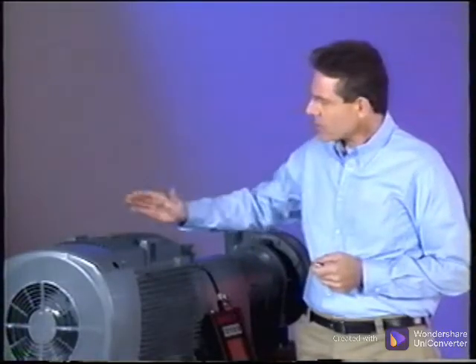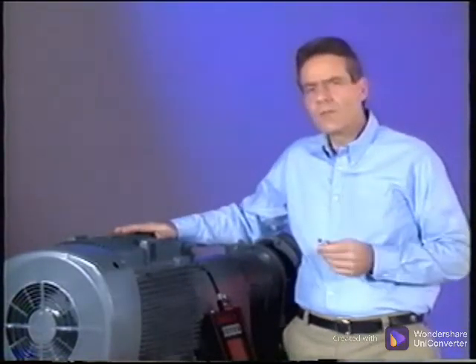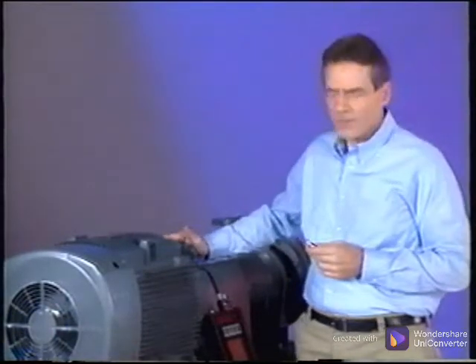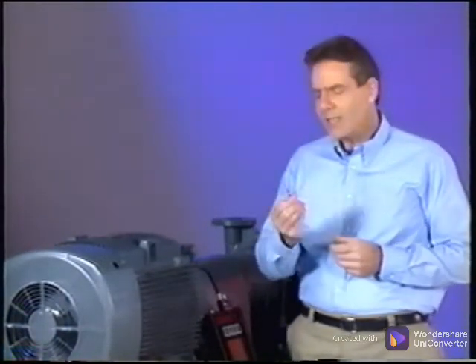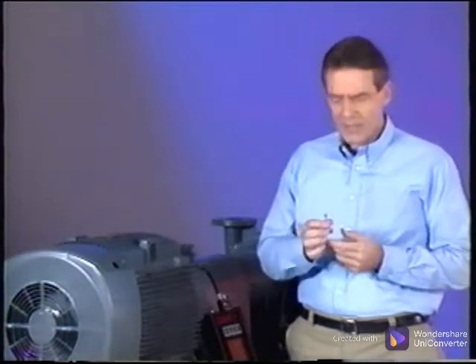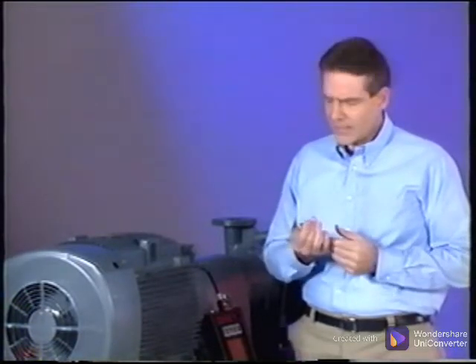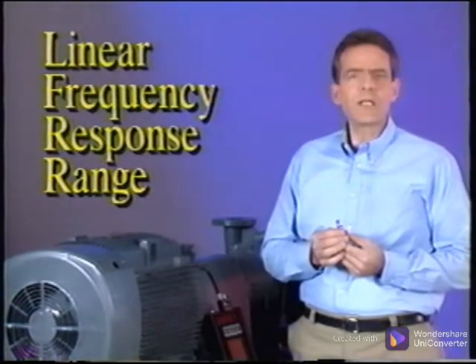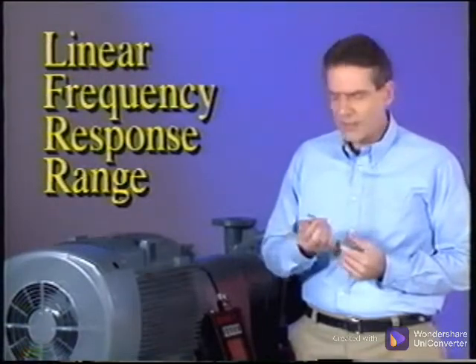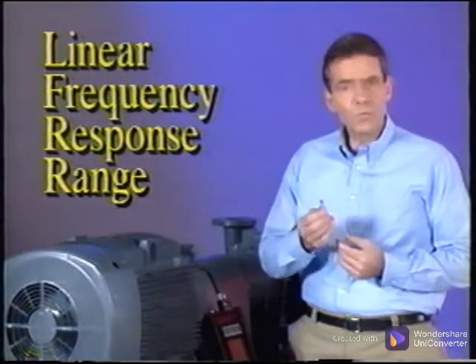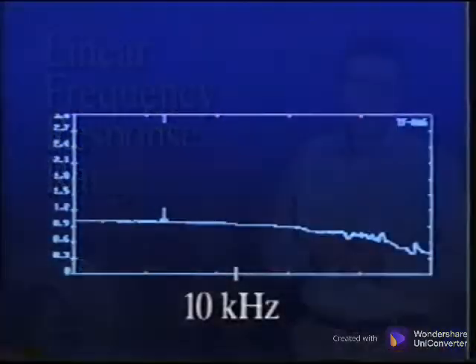If you know the internal structure of the machine, collect the data where there will be a good solid path to the transducer. We need to use the characteristics of the sensor to maximize our results. Other limitations are built into the transducers that affect our data. One of these limitations is the linear frequency response range. Sensors are designed to function well in certain frequency ranges.